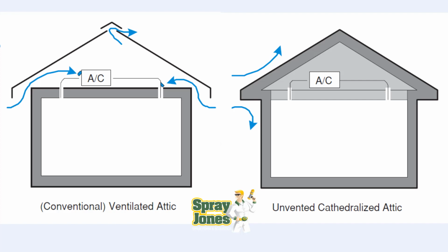And at that point, we've had the code inspectors treat that as a standalone area that is meeting the thermal barrier requirements, and then the rest of the attic space or crawl space, this would apply to crawl spaces, doesn't need to be spray-on thermal barriered, and that's probably the best way to go when you're running your equipment up inside there. I've just not seen it where we've gotten all of the equipment installed, whether it's in the attic or elsewhere, and then the heating loads have just been out of whack.